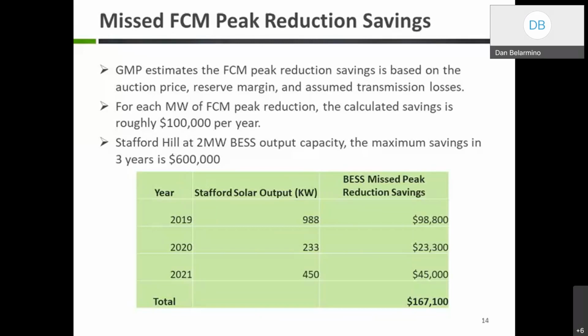So, for the purpose of comparing the lost value of DC coupled versus AC coupled systems: Stafford Hill has a 2 megawatt output capacity, so if it could use its full battery output capacity, maximum savings over 3 years would be about 600,000. But since it's limited by solar output, we estimate about $160,000 in value is lost because it's curtailed or limited by the solar.